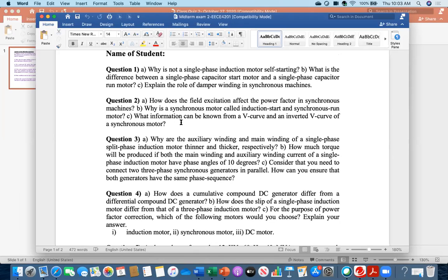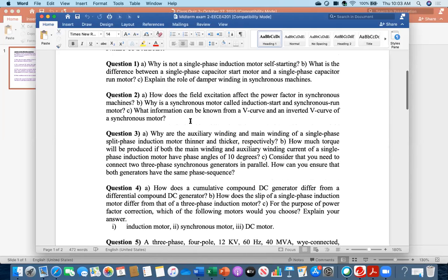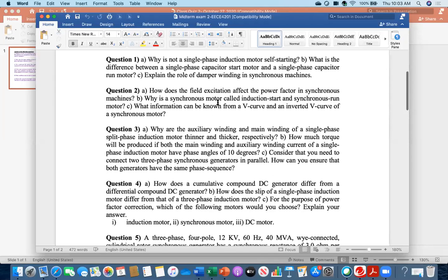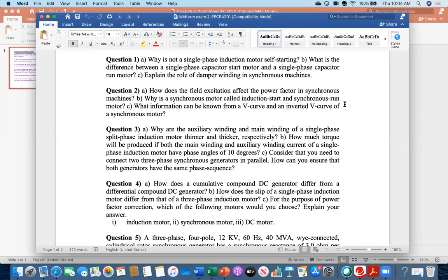Part b: why is the synchronous motor called an induction start, synchronous run motor? Because like the single-phase induction motor it is not self-starting, so the damper winding starts the motor using the induction principle. Once the motor locks onto the synchronous speed of the field, it runs at constant synchronous speed.